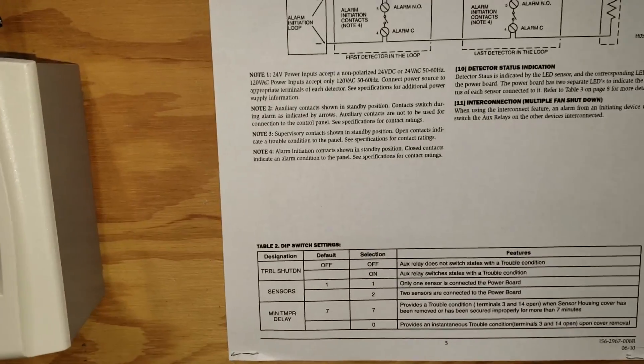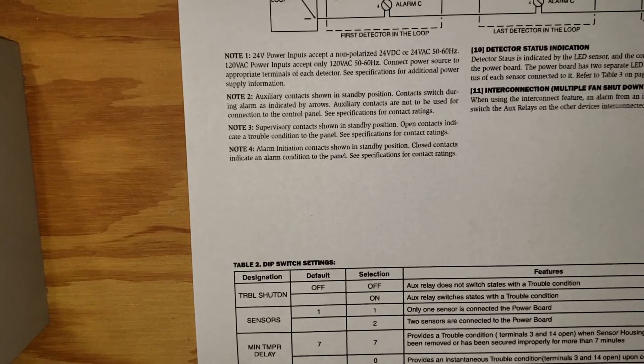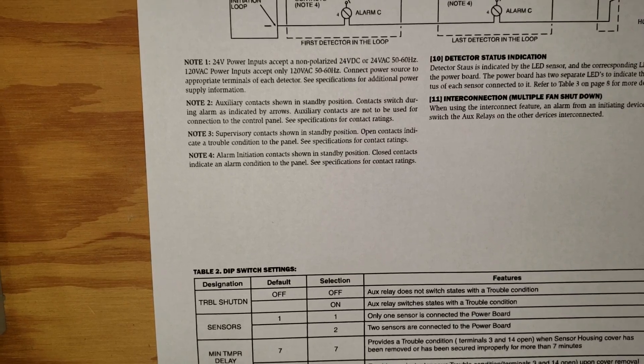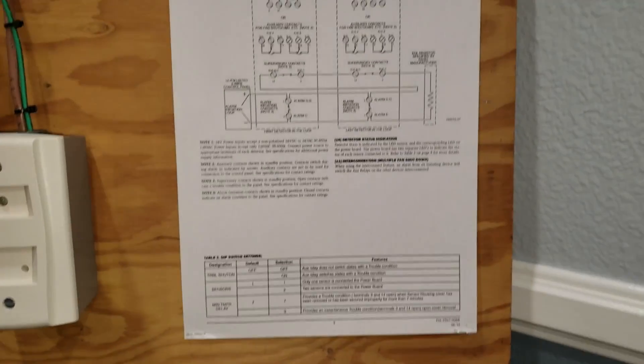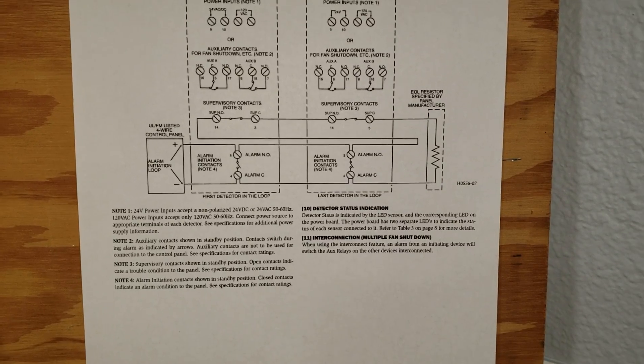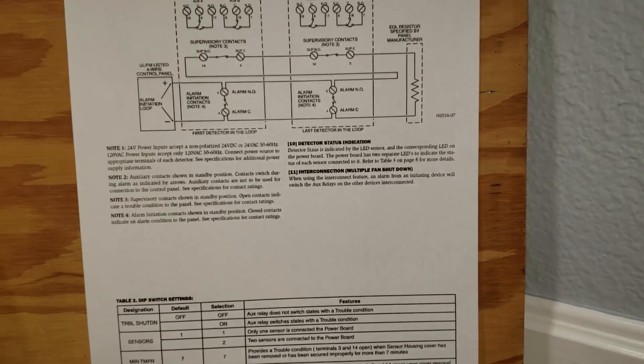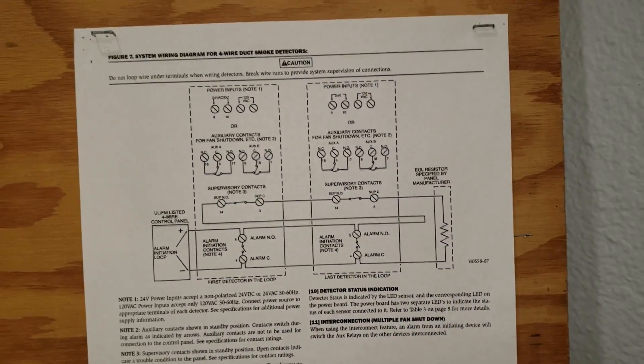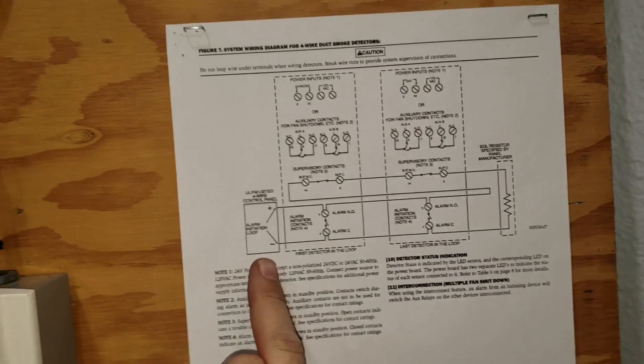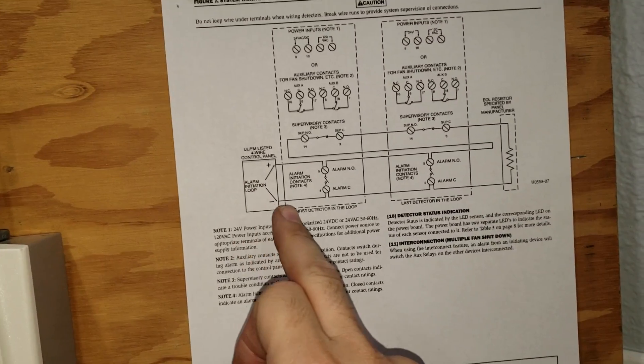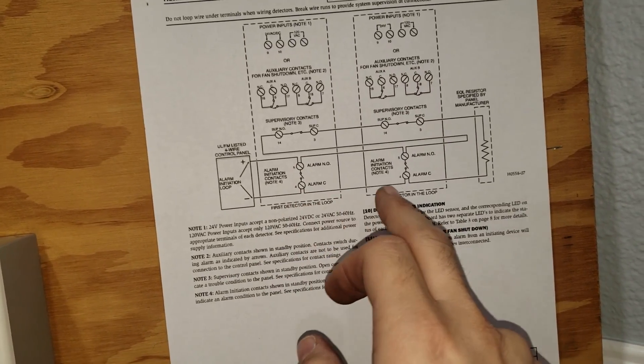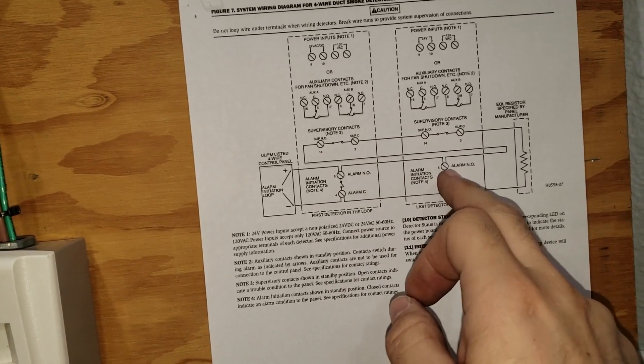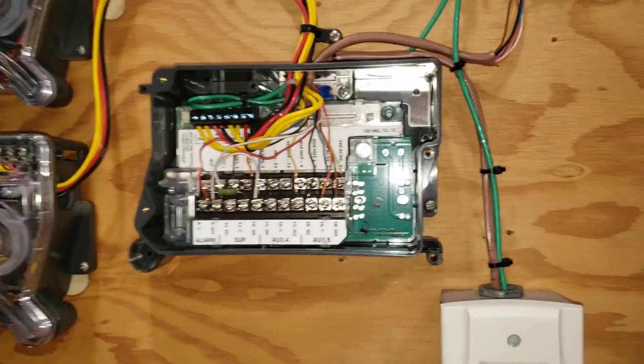I'm going to point out something on this sheet. If you read the note, number three is what I read off to you earlier — supervisory contact shown in standby position, open contacts indicate a trouble condition to the panel. This is the schematic to wire up this detector, and notice the way I wired in that resistor — it actually tells you how to do that right here in the schematic. All I did was follow this schematic exactly: took my initiation loop wires from my alarm, ran them across the alarm contacts, but also ran the resistor through the supervisory contacts, common and normally open, and then back to the contacts.